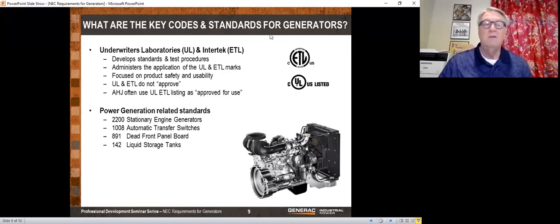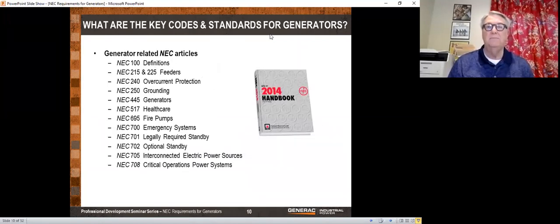And if you don't have a sticker on the generator, it's pretty tough to get one on there because if it's not built to UL, then you got a real problem. If it is built and you have to apply the sticker, you can't just do that in the field. You'd have to have a custom UL inspection or send it back to the factory. Transfer switches also have a UL. Engine generators are 2200, transfer switches 1008. That's only for low voltage, by the way. And then you've got your panel boards, and the tanks have their own standard.